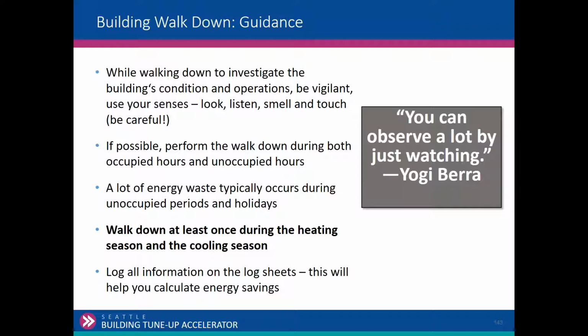So when nobody's there. In a perfect world, we'd walk the building in the heating season and in the cooling season. We do have some time frame to get these reports into Nicole that spans those two seasons. But we're looking at different things. During the heating season, for the most part, our buildings are heating dominated. Here, we use more energy for heating. And so our infrared camera, our air leakage, boiler water resets, those are the issues. As we transition into the cooling season, now we're looking at economizer, chiller operation, cooling tower operation. So ideally, we would do our observations and our tune-ups in both of those seasons.